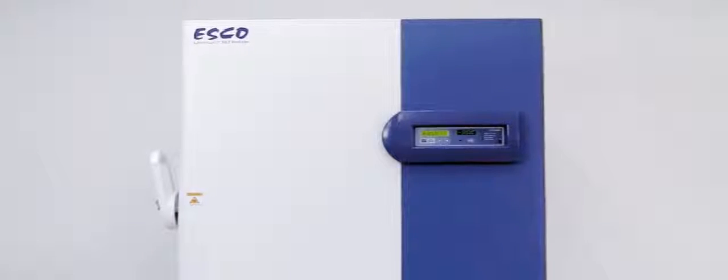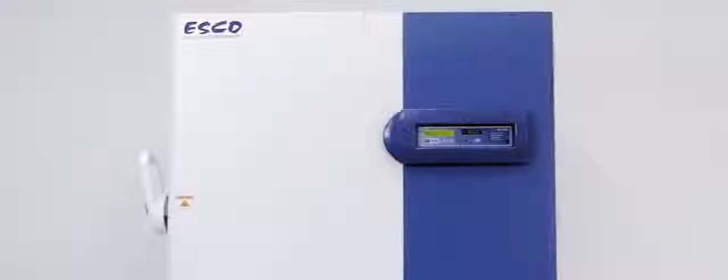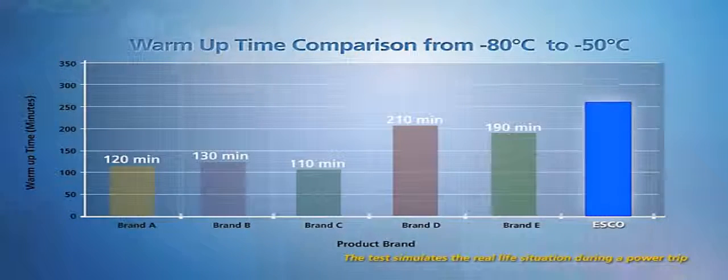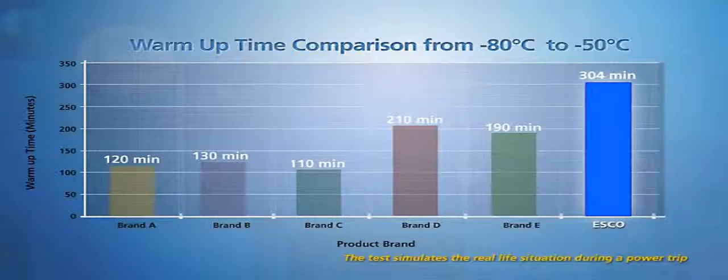Warm up time measures the time taken for temperature to rise up from minus 80 degrees Celsius to minus 50 degrees Celsius when the power is interrupted. A longer warm up time preserves samples longer during power failure conditions. Esco has the longest warm up time among the freezers compared to other brands.